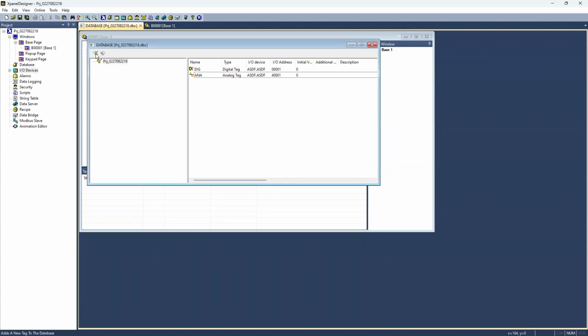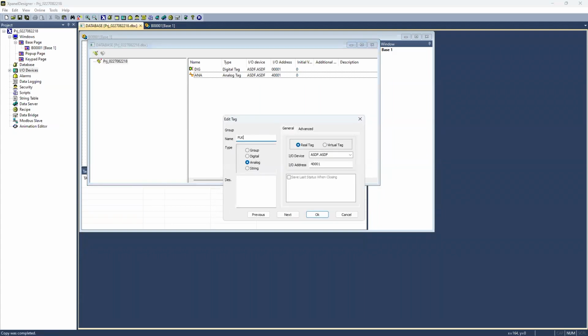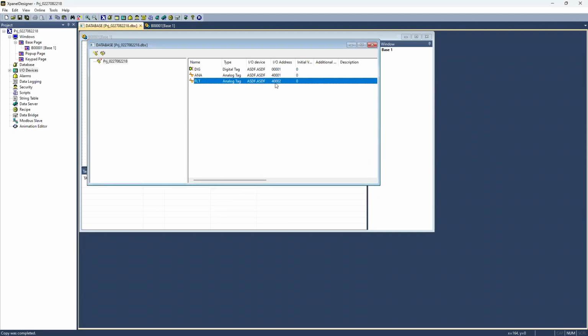Now, what if I wanted to talk to a float over ModBus? I mentioned this earlier, but I just want to reiterate it. Let's say we target 40,002 as a float. If we come over here, we have to target it as a float. So we choose float. What does that entail? 40,002 and 40,003 are going to come along for the ride when we're talking to this ModBus address. It's going to take both of those registers and combine them together, and then it will decipher the orientation of the bits and produce the correct float.